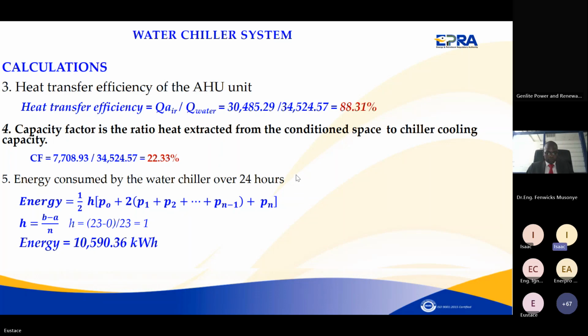It is underutilized, I would say. If they add more load, they would handle maybe to get to 75%. Let's start from the first thing. If there's the load, if there's the heat I'm supposed to remove, 7,000 from the room, I don't require to run the whole chiller. Probably the chiller compressors, the control system has failed such that it's not detecting when the load is going down or up. So it's being inefficient.